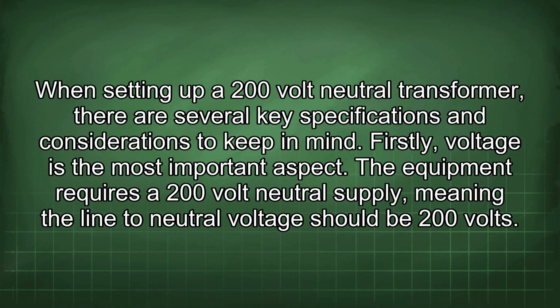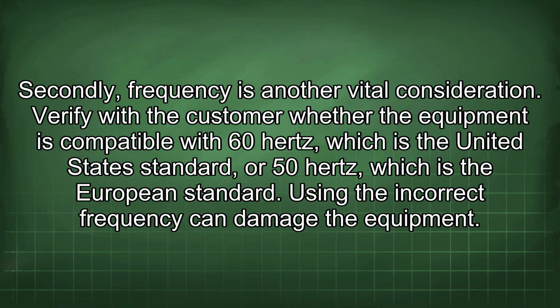When setting up a 200-volt neutral transformer, there are several key specifications and considerations to keep in mind. Firstly, voltage is the most important aspect. The equipment requires a 200-volt neutral supply, meaning the line to neutral voltage should be 200 volts. Secondly, frequency is another vital consideration. Verify with the customer whether the equipment is compatible with 60 Hz, which is the United States standard, or 50 Hz, which is the European standard. Using the incorrect frequency can damage the equipment.